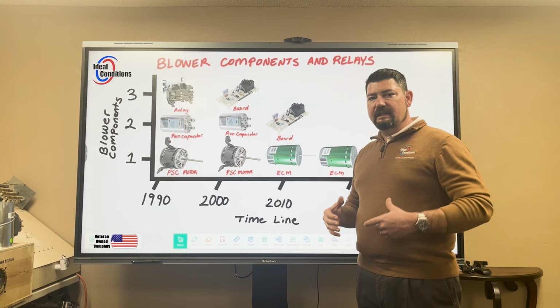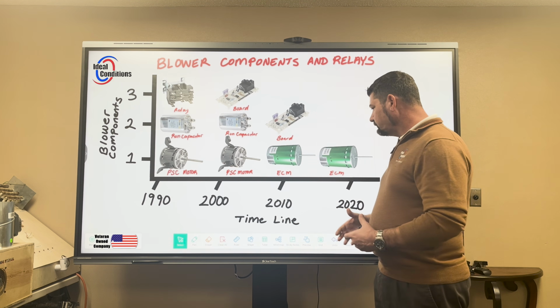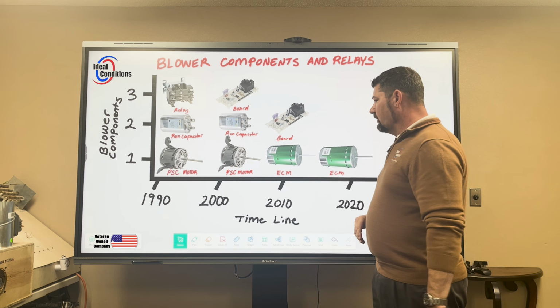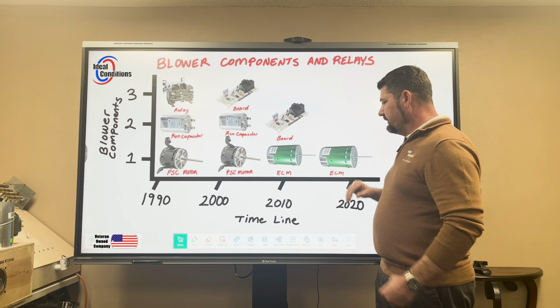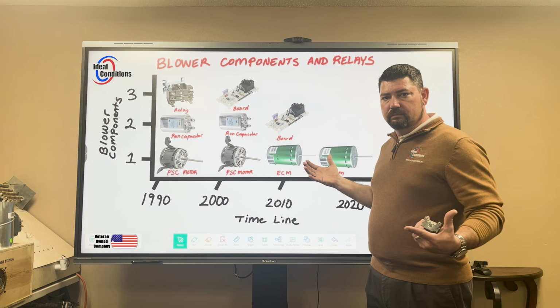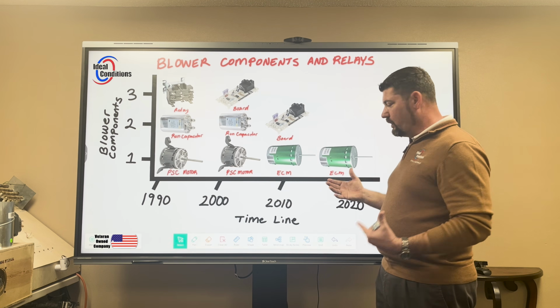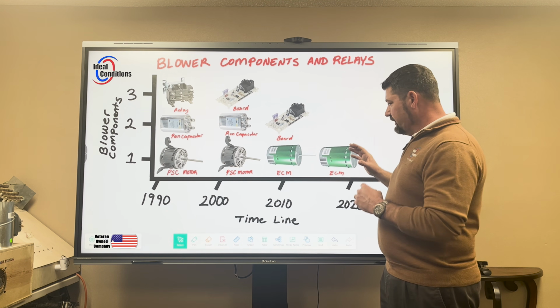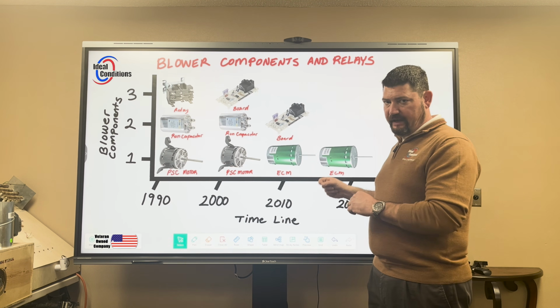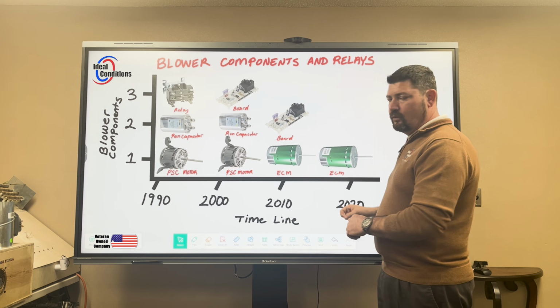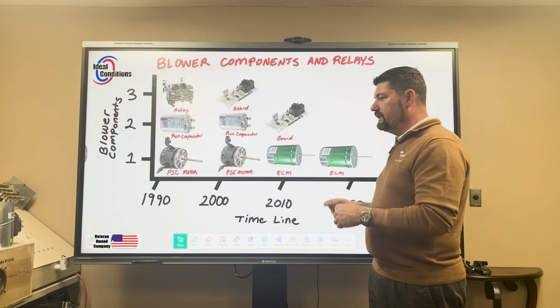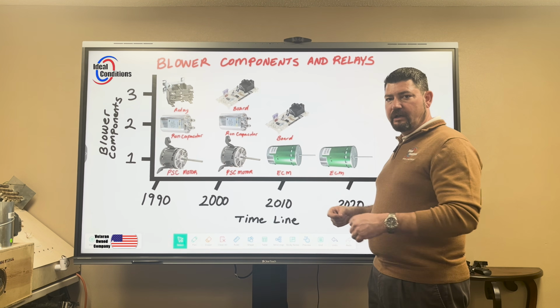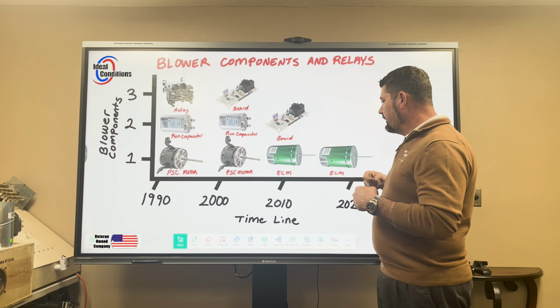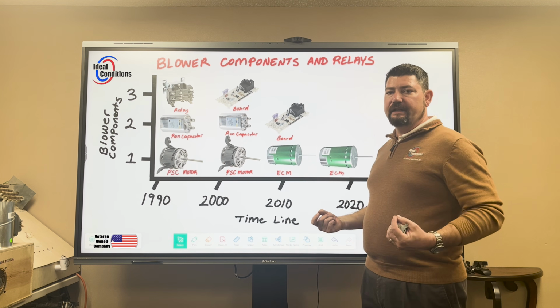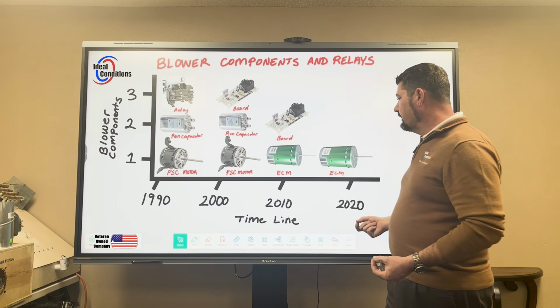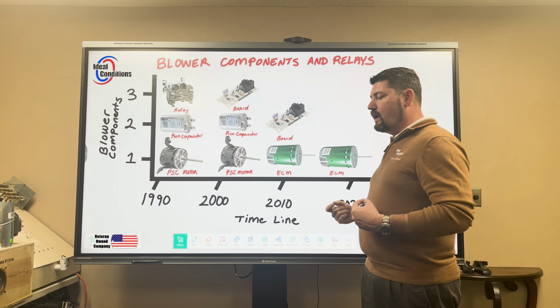That's not a bad thing. If the customer's under warranty, get them up and running with the module or motor, whichever component it needs. But you also want to look at what caused it to fail, because you don't want to repeat that process every 6 months or a year, constantly replacing motors because they're failing due to high static pressures, or because things just aren't wired properly.